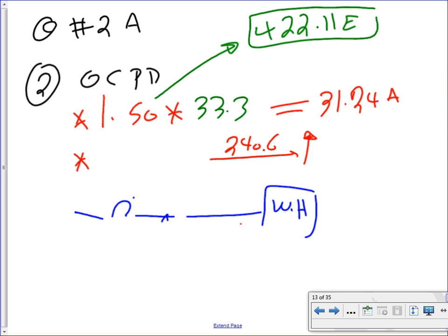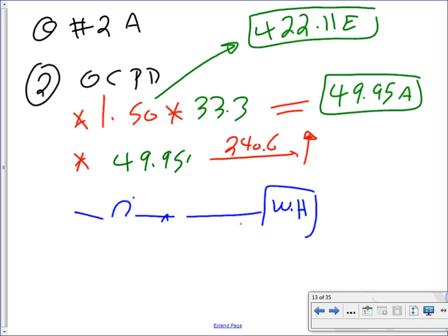33.3 multiplied by 1.50. That will get you, okay, what am I, okay. That will get you, this is wrong here, of course. That will get you 50. Am I right here, 50 amp? Can you guys check that one for me? 50 amp. Anybody verified that math? Yeah, 49.95. Okay, let's use 49.95, just to make sure. So then you take the 49.95 amp. That'll get you a healthy 50 amp. So that's my 50 amp circuit breaker.